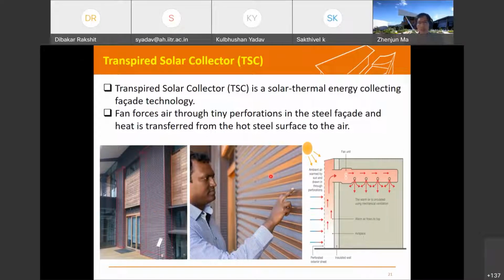You can see a lot of small holes on this facade. We usually have a fan on the top - when the fan is in operation, it sucks the air through these small holes. Because of the solar radiation, it heats up the air in the channel, so the air temperature increases, and at the top this area may reach 50 degrees centigrade. Then you can direct this air into the space for space heating.